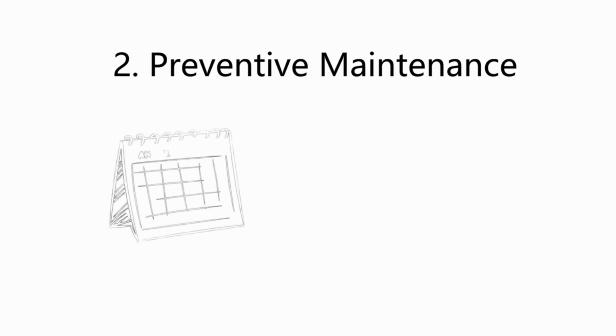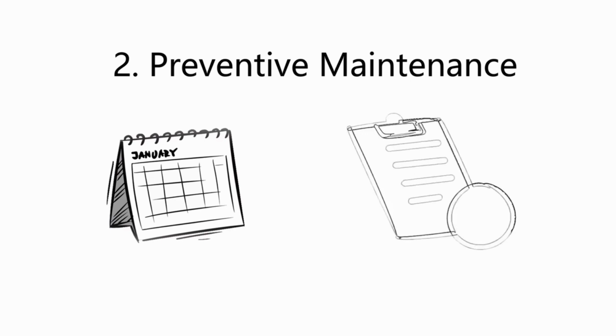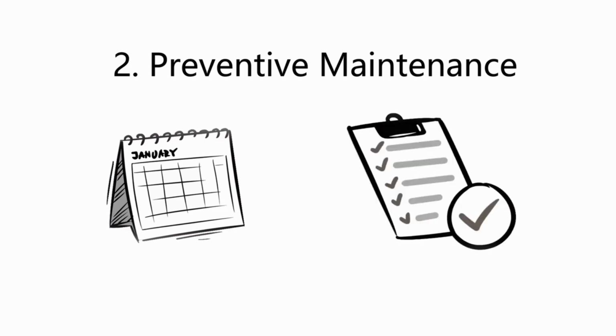2. Preventive maintenance. Maintenance carried out at predetermined intervals or according to prescribed criteria, aimed at reducing the failure risk or performance degradation of the equipment. The maintenance cycles are planned according to the need to take the device out of service. The incidence of operating faults is reduced.